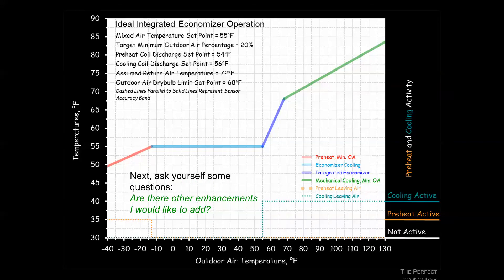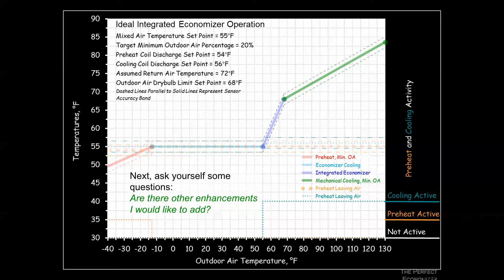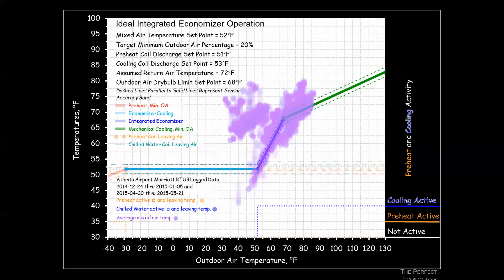Understanding that dry bulb temperature sensors have inherent inaccuracy, we add dashed lines to show the tolerance band around the perfect economizer profile. Now, plotting actual performance data against this ideal profile lets us quickly assess the health of our actual economizer.